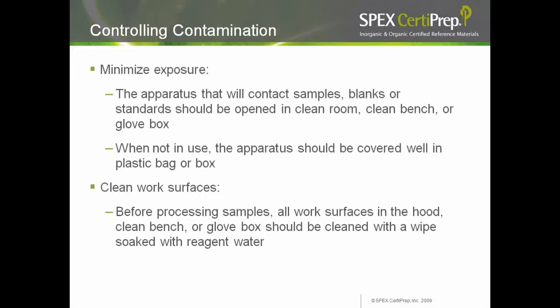So how do we control contamination? We must minimize exposure. Apparatus that will contact samples, blanks, or standards should be opened in a clean room, clean bench, or glove box, and when not in use, kept covered in a plastic bag or box. We must clean work surfaces more frequently. Before processing samples, all work surfaces in the hood, clean bench, and glove box should be cleaned with a lint-free wipe soaked with reagent water.